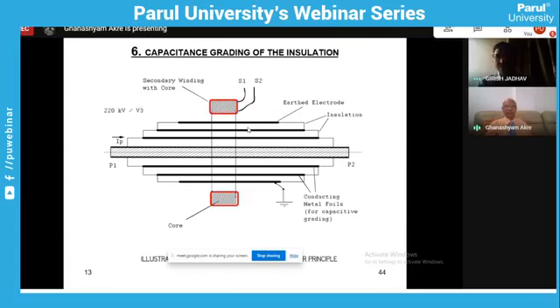You see the primary and there are two secondaries. The primary has a larger number of turns while the secondaries have fewer turns. The primary is a fine gauge wire, maybe 30-35 gauge, with thousands of turns, connected across the primary. The general cross section is like what you see, and this is the shape of the VT. At the bottom it is a core winding, insulated properly, and again taken up at the top. This is 220 kV, and this is a cross section of the VT. So, friends, I will stop here for the construction, and let the question and answer session be there so that I can clear more doubts.